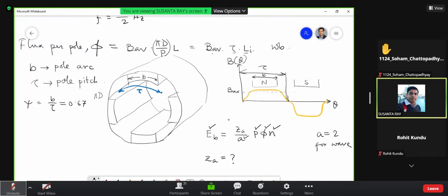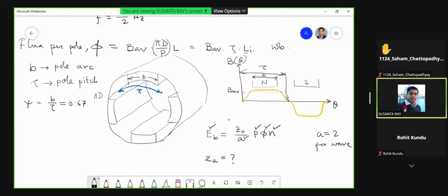If you go for 70 hertz, then your eddy current loss will be quite high, and also the hysteresis loss. Better you take more number of poles. Instead of 6, you take 8. If I take number of poles greater than 6, then I will not get D and L nearly equal. There will be a huge difference between L and D, sir.